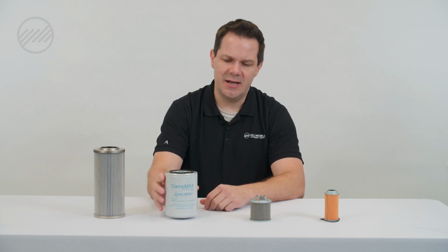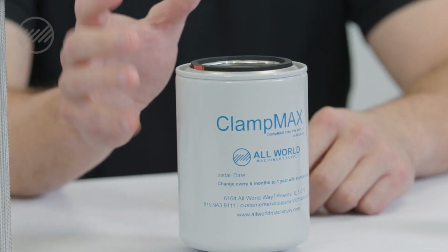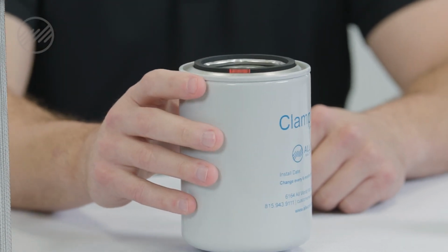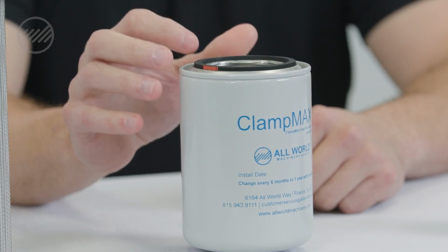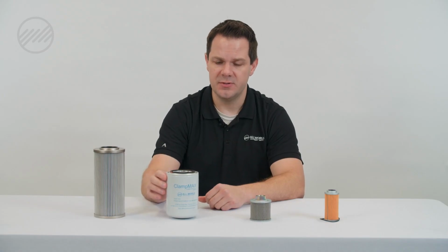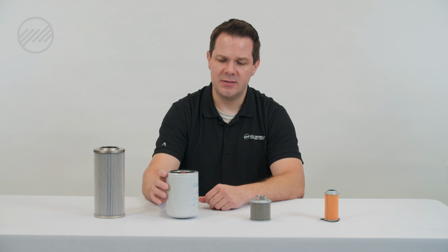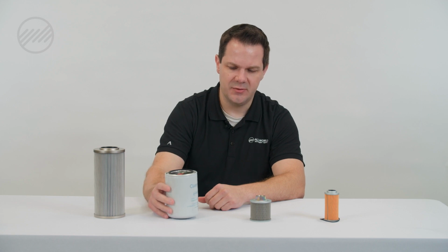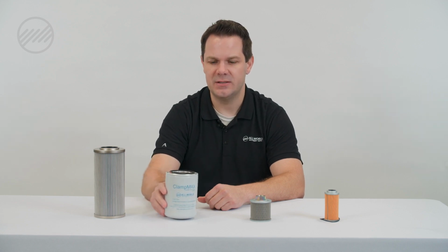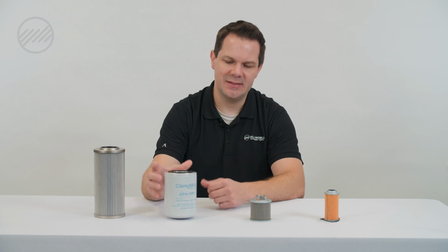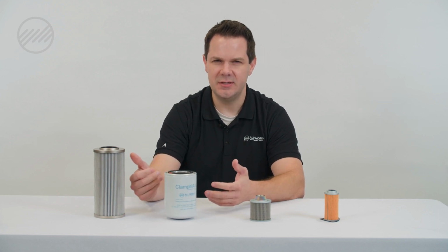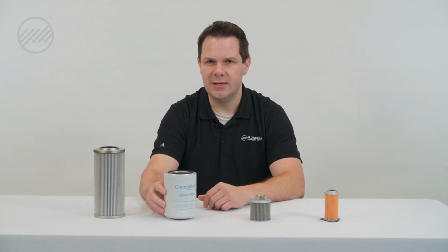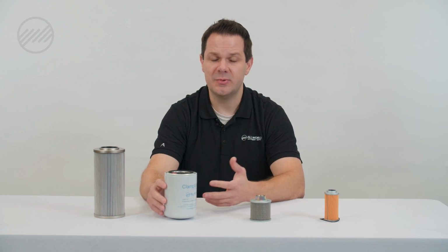So a lot of these will have indicators that are on the top of the filter head, which would be up here, that tell us when this is plugged or when there's been a loss of flow or a buildup of pressure through this filter. It can be a visual indication or it can be an electronic indication. This particular filter is your typical 10 micron screw-on filter, and something like this, regardless of installation being used in a hydraulic system, you would be replacing in 6-month or 12-month increments for your typical conditions.